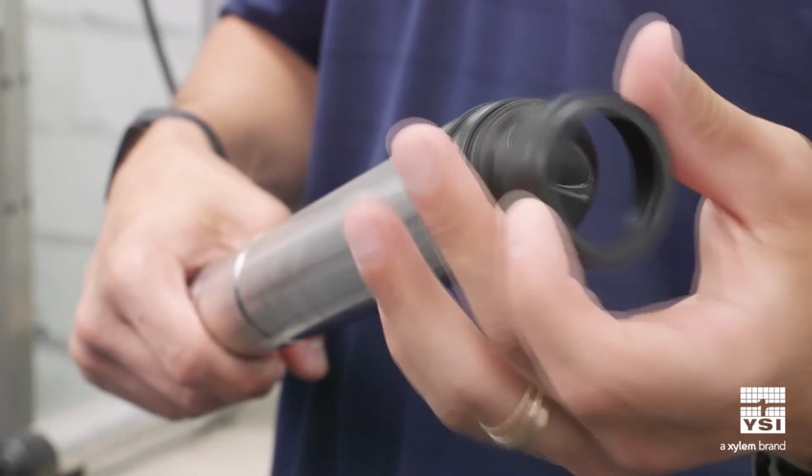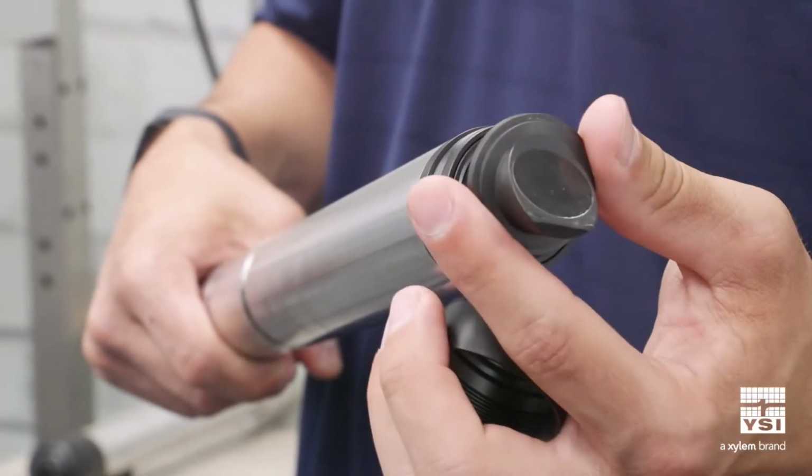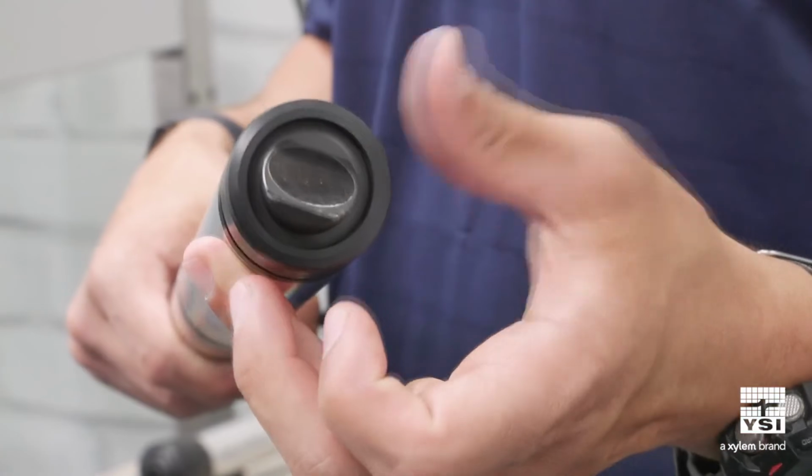So I hear from our clients that a common way IQ SensorNet is used is to help with energy savings. Now, how exactly does analytical equipment do that? That's correct. Plant energy costs can be expensive if not managed. For example, in an aeration basin, blowers that are constantly running use a lot of energy, and all of that energy costs money. In a lot of cases, facilities are over-aerating their process to ensure they are meeting compliance. By using an online DO measurement with YSI's FDO dissolved oxygen sensor, a plant can control its aeration process more efficiently by choosing a DO set point, and the blowers can be automatically adjusted based on the sensor's measurement.